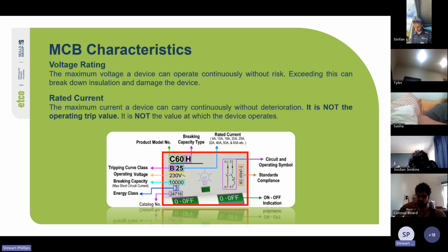Cool. So it's rated current, the maximum current the device can carry continuously. Its maximum breaking capacity is 10,000. It is not the value at which the device operates.